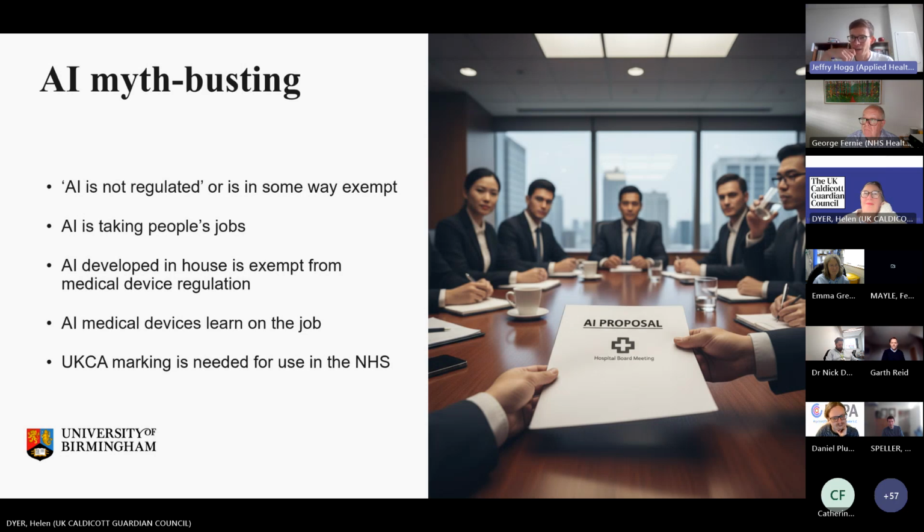Everything on the market, as I understand it, is fixed in the medical device space, because once it's done some learning, it's essentially a new product and it needs to go through the 18-month regulatory approval cycle again. Now, there are changes coming, both in terms of technologies and the regulatory approach, that might make that not the case in the future, but it's something to be aware of at present.